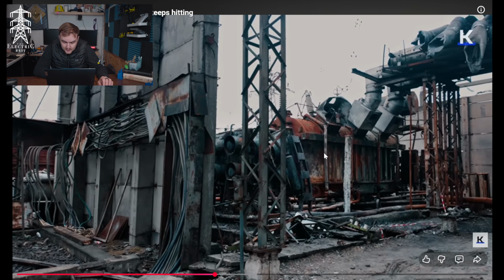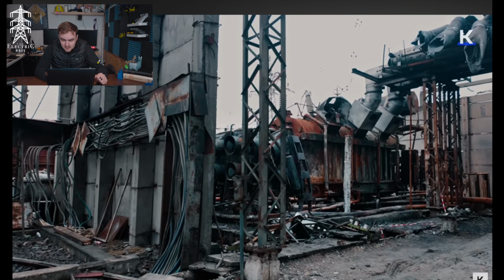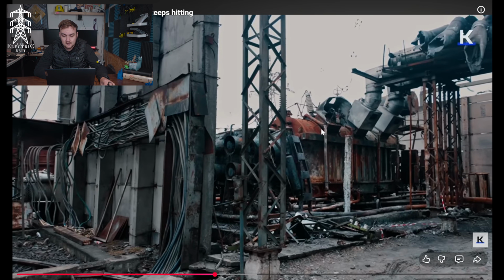Looking at the transformer in general, the top of it started to rust, so it's been damaged for quite some time. Obviously, looking at this, it's a mess, so it's been destroyed at some point, and that tells me this has caught fire. All the paint's been destroyed off it, and then it began to rust.